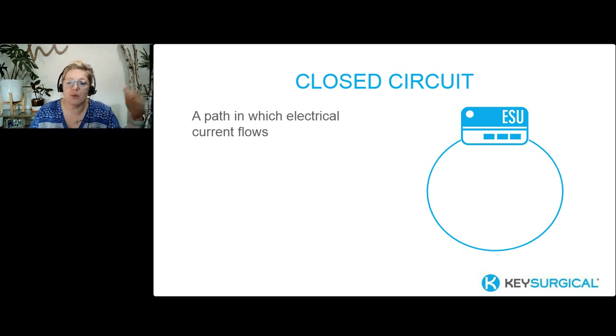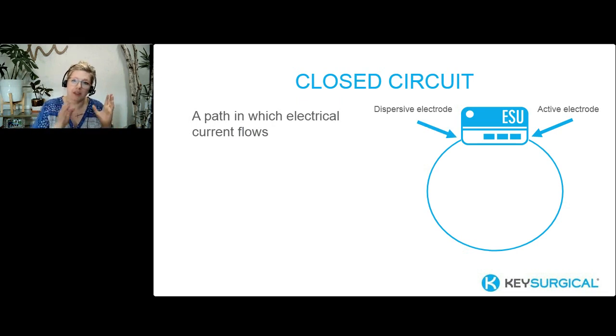So the first thing that we have with creating our closed circuit, we have our ESU, right? That's our voltage, gets things going. We have our active electrode. Usually this is our instrument, what we're using to apply that electrical current to this patient's body. And then we have our dispersive electrode. Some people call it a return electrode. And this can either be within the instrument itself, which we're going to look at in a second, or it can be a pad that's placed externally on the patient. You guys know exactly what I'm alluding to.